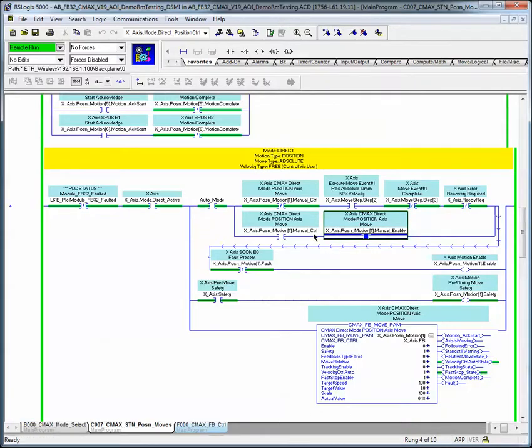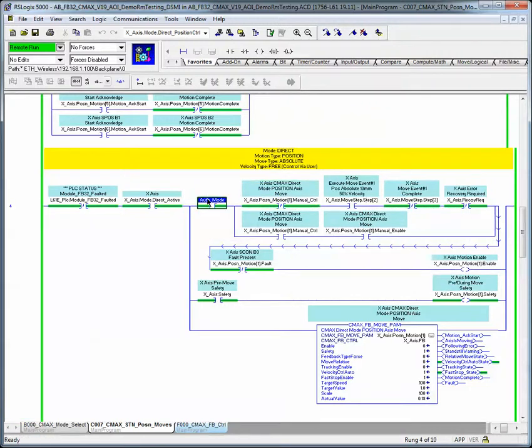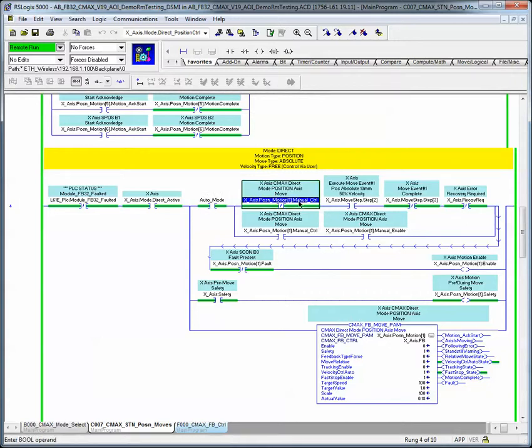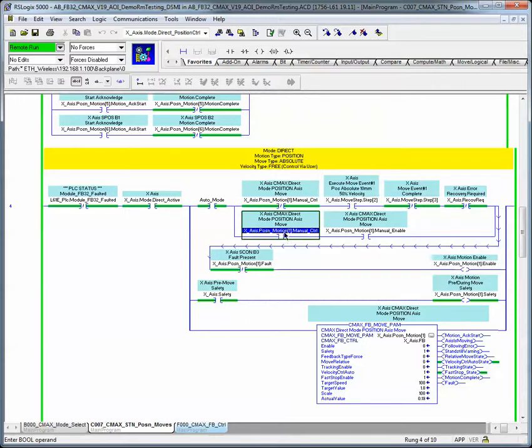I'm just going to show you one move here. I've got a sequence in here that runs while we're in auto mode — this is when all these functions work. When you're in auto and we're not in manual control, the sequence will operate on this. Otherwise, if you want to operate this manually, you can set and control these bits on.